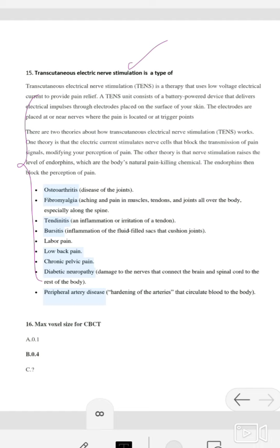And maximum voxel size for CBCT, so it's going to be 0.4. So what is a voxel? A voxel is nothing but the smallest 3D element of the volume, and it is typically represented as a cube or a box, right? With height, width and length. There are different voxel sizes depending upon the capabilities of each unit. Smaller field of view units may use a smaller voxel size of around 0.076, which enables visualization of very small changes. You have other voxel sizes also like 0.2, 0.3, 0.4.